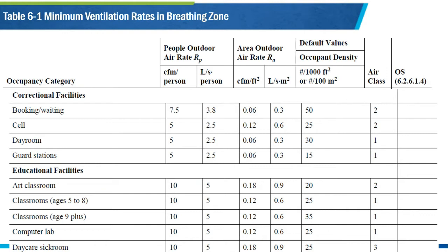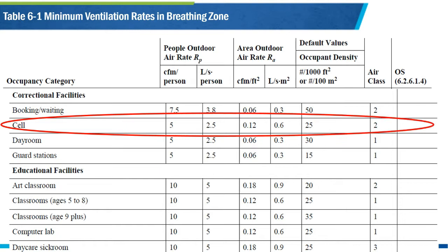For this example, this is a partial list from ASHRAE 62.1 showing the minimum ventilation rate for jails and schools. What's shown here on the left is the occupancy category and the amount of air required per person in that space. This table shows the occupancy categories correctional facility and educational facilities. This table is showing a minimum ventilation rate for a jail cell requires only 5 CFM per person plus 0.12 CFM per square foot of space, with a maximum occupancy of 25 people per 1,000 square foot.